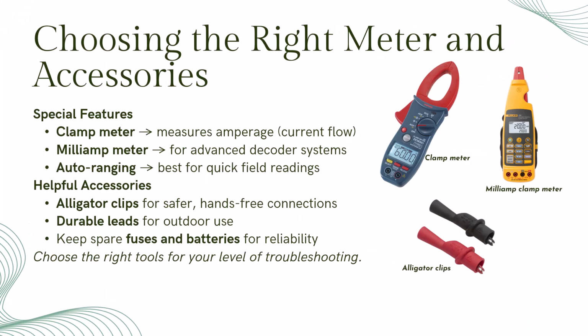Beyond the basic multimeter, there are a few features that make troubleshooting easier and safer. If you're diagnosing pumps or have been trained to use amperage readings effectively, a multimeter with a clamp meter is a must. It allows you to measure current flow safely without disconnecting wires. For more advanced systems like 2-wire decoder setups, a milliamp meter may be required. These are specialized tools for precise low current measurements.